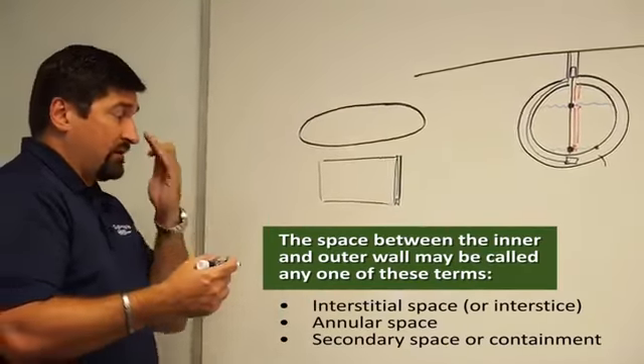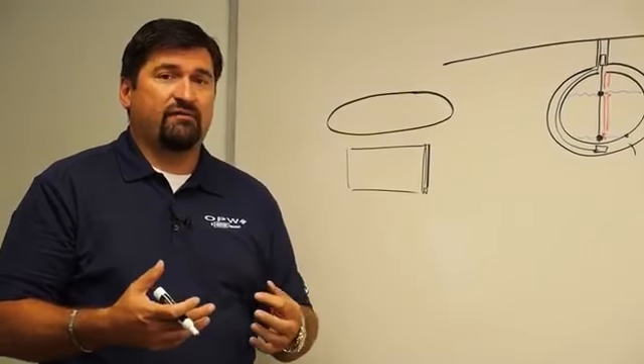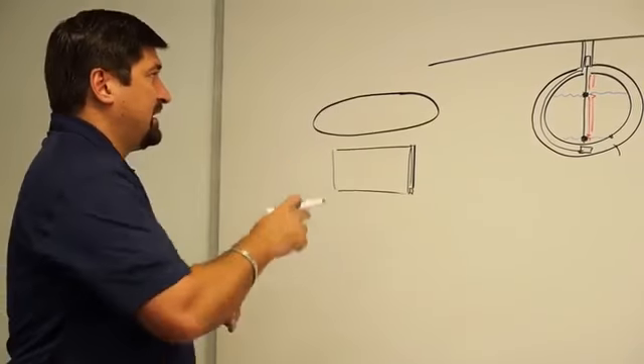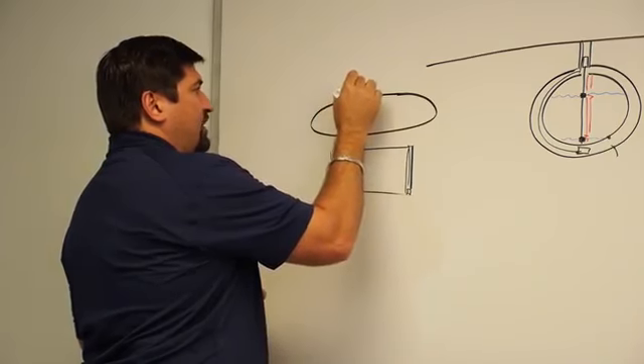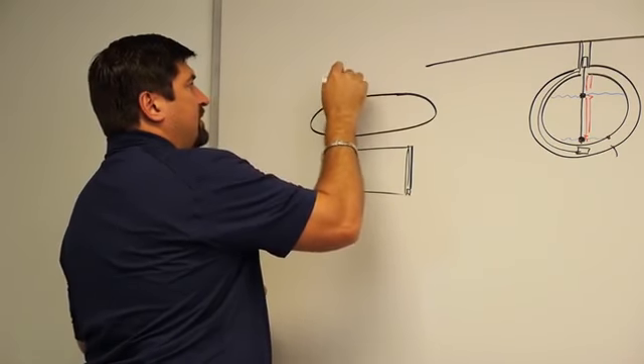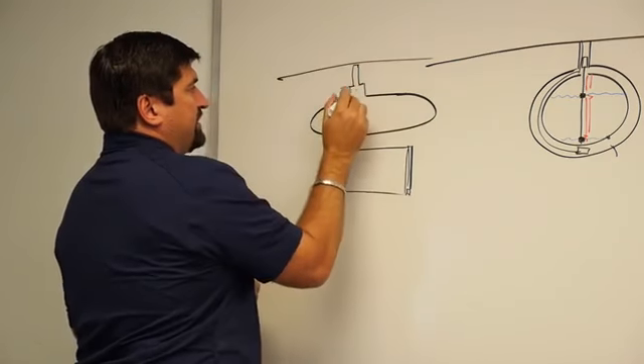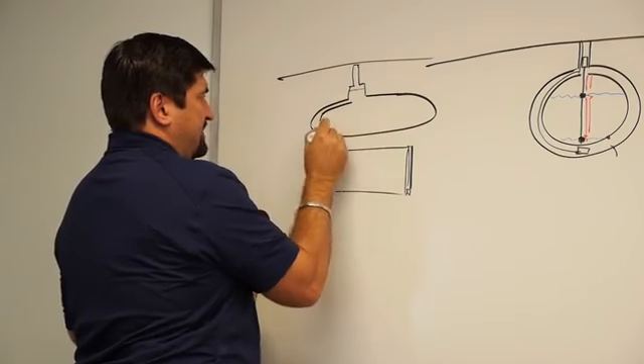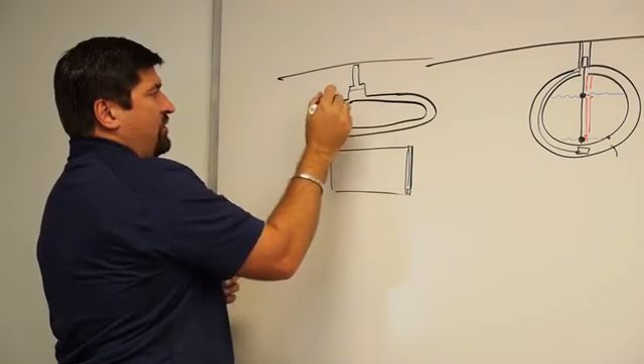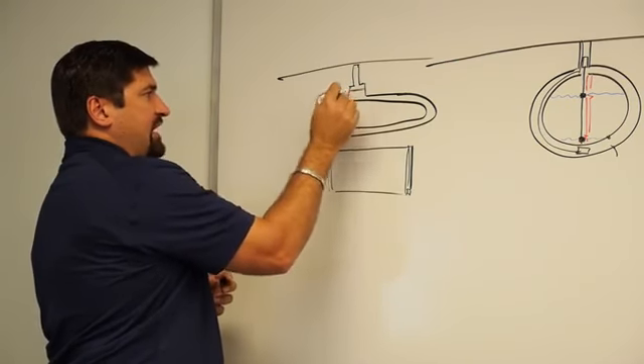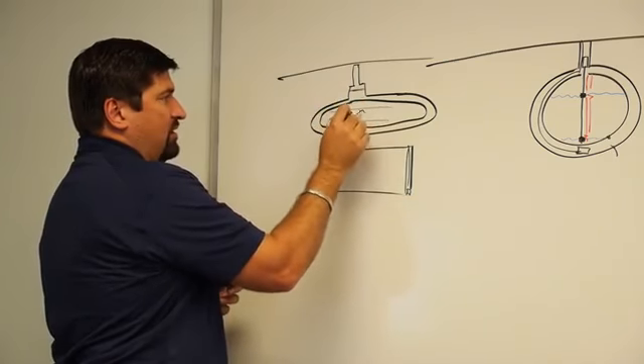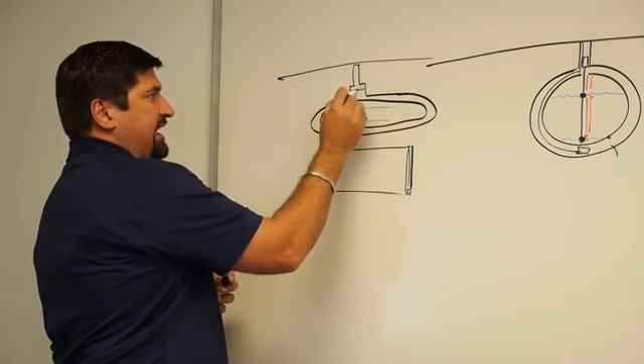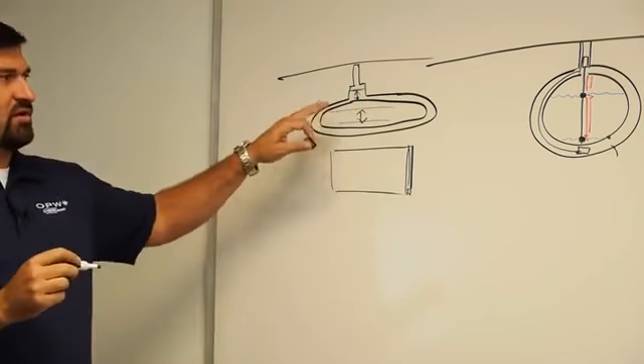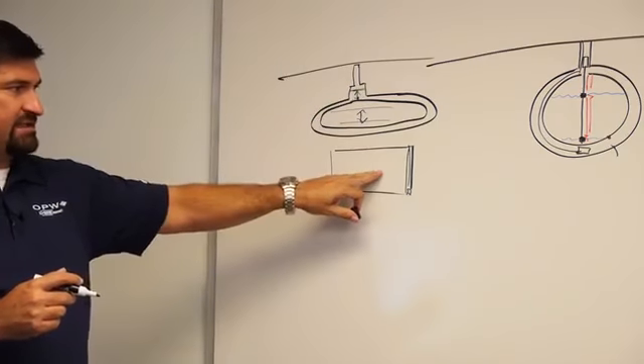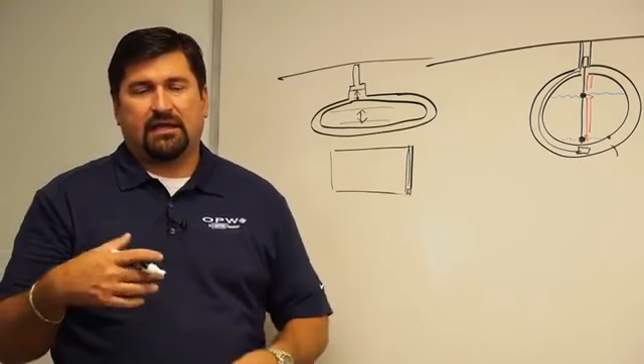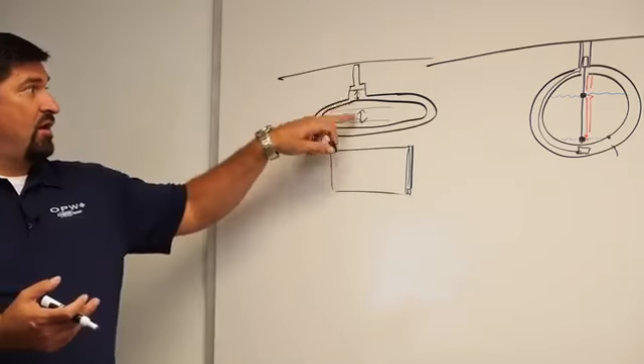The most common one that you're seeing now is actually going into what's known as a brine-filled or a glycol-filled annular space. Now the glycol-filled tank will actually have a reservoir built on the top of it with a vent pipe up to the surface. So what they'll do is fill this up with glycol, and then you have the secondary of the tank. The problem that most people run into with this is they don't set this glycol level correctly. As I fill and lower this inner tank, it expands and contracts, and it causes this fluid to rise and fall. But this is known as a brine or glycol annular tank. A steel tank annular or a fiberglass dry annular can either be done through a float type switch, an optical switch, or a dual float reservoir switch.